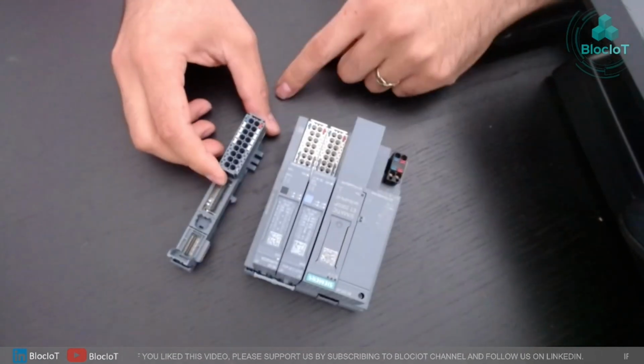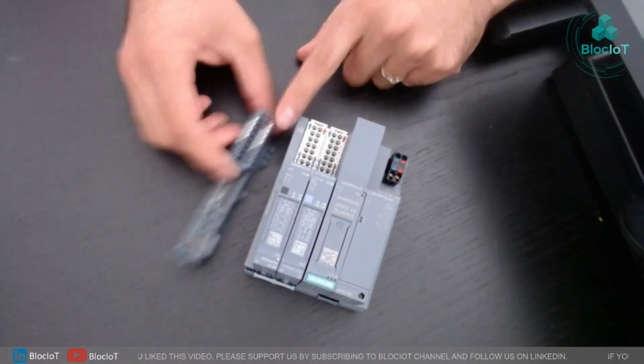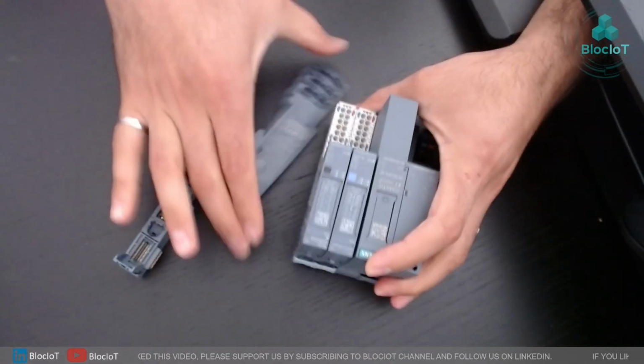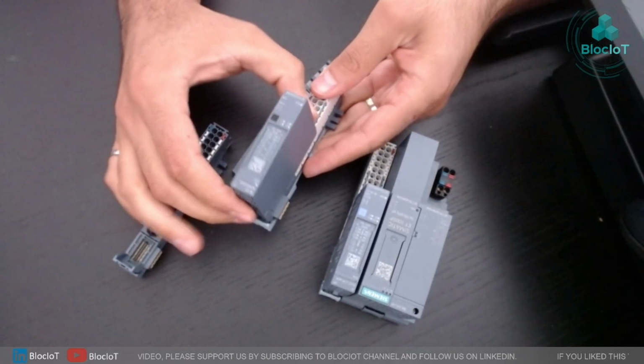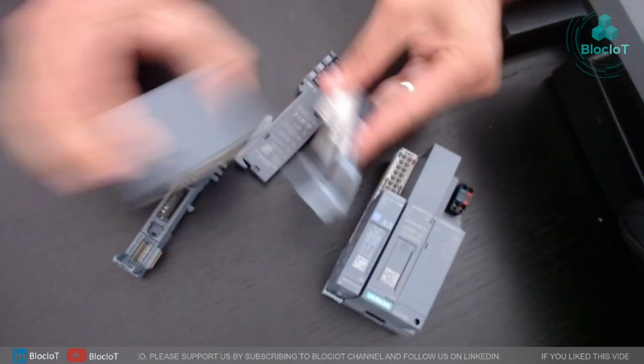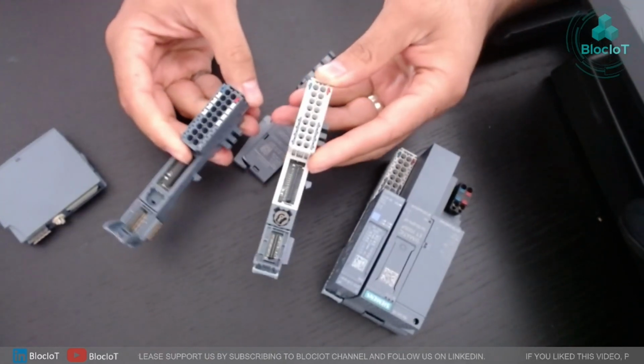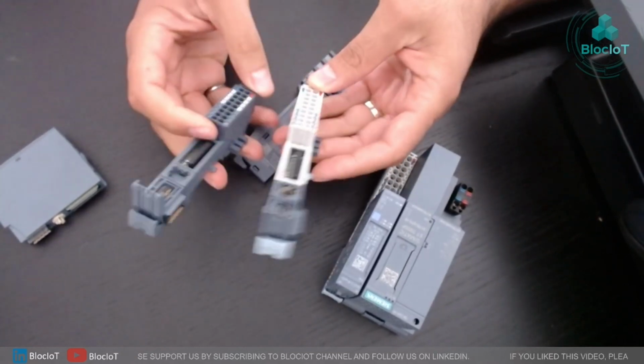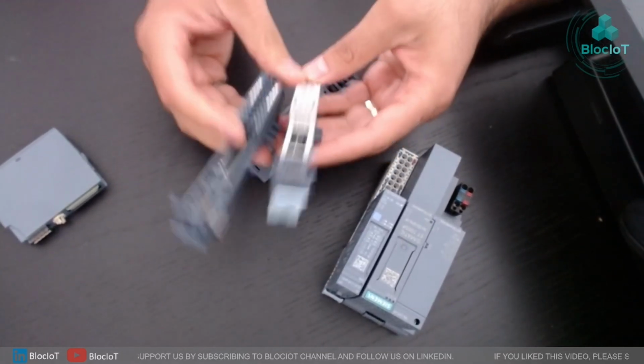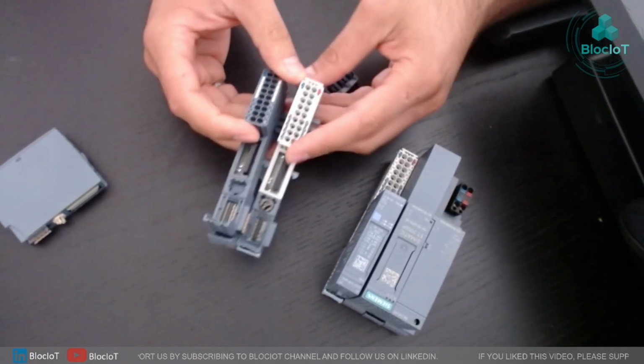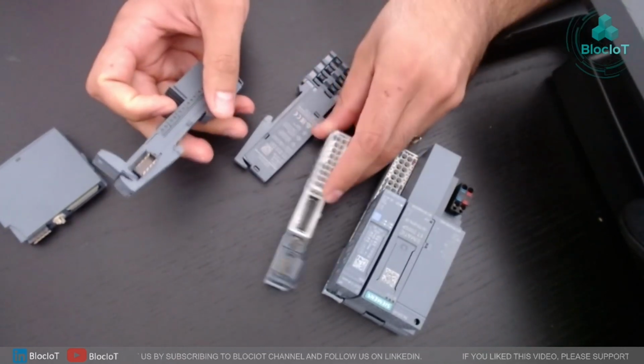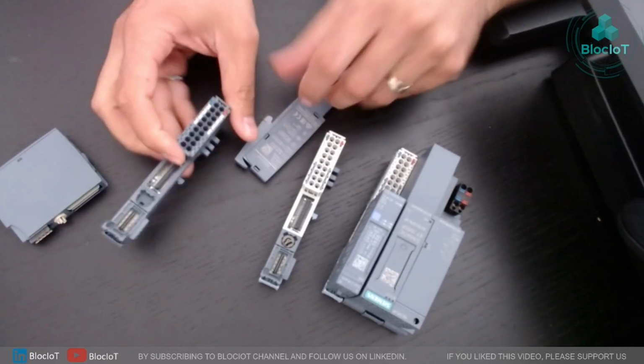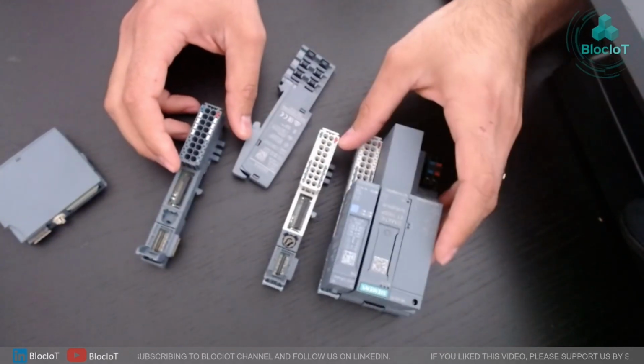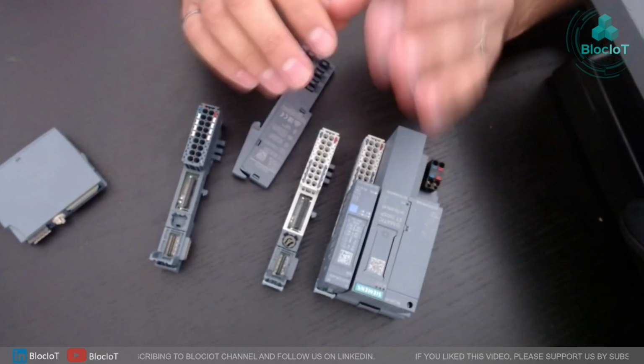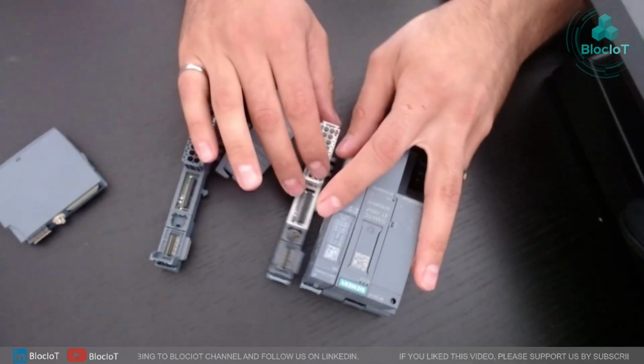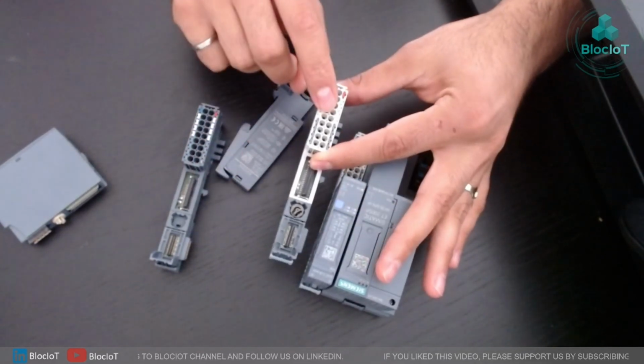You might have noticed there are different types of base modules, and here I have both of them, and you can recognize them by the color. As you see here, I have a white base module and a gray one, and the difference between them is basically the power distribution. Overall, in a nutshell, the white module is used to distribute the power. In the older ET200S, we had something called power modules that do not exist in ET200SP, and the power distribution is done through the white modules.